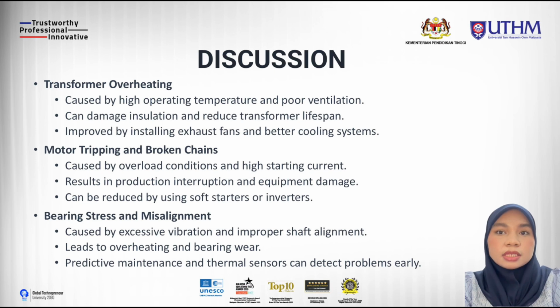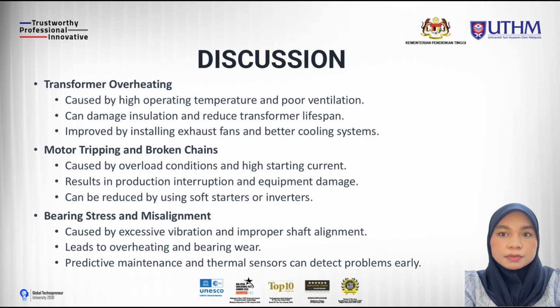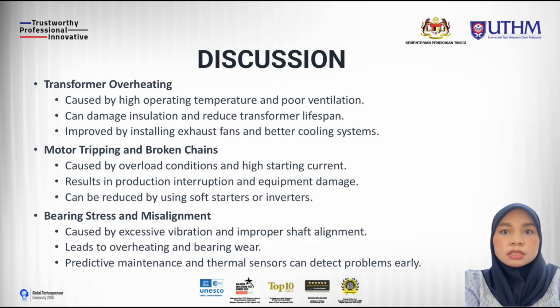Lastly, bearing stress and misalignment are usually caused by excessive vibration and improper shaft alignment. This condition can lead to overheating and bearing wear. Predictive maintenance and thermal sensors can be used to detect problems early and prevent serious damage.